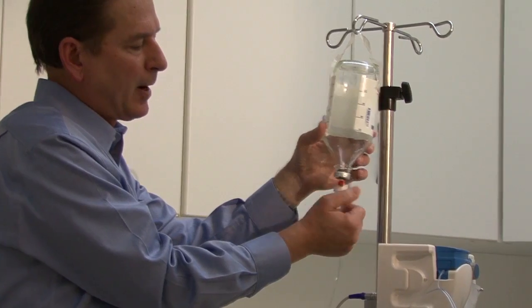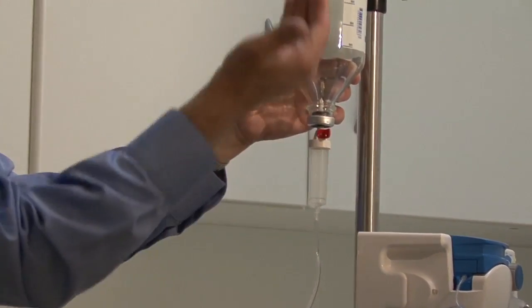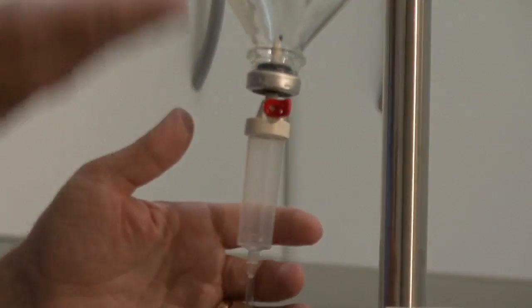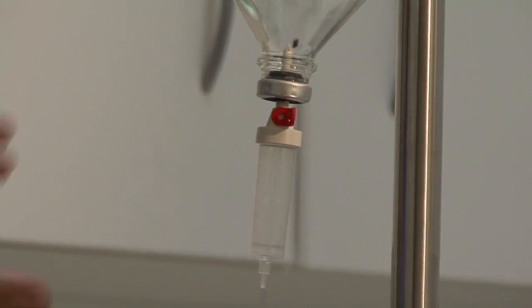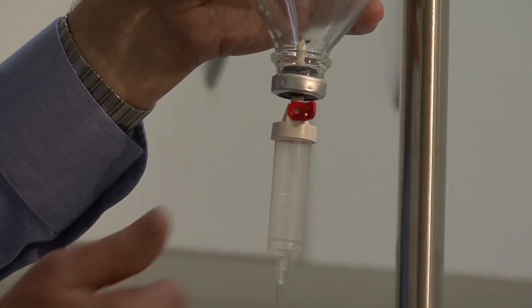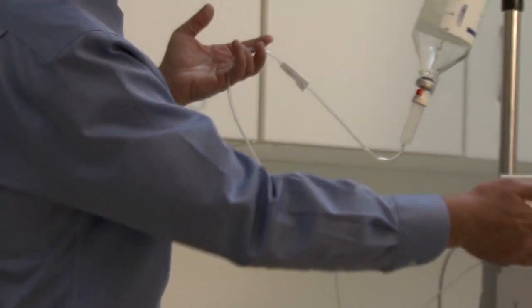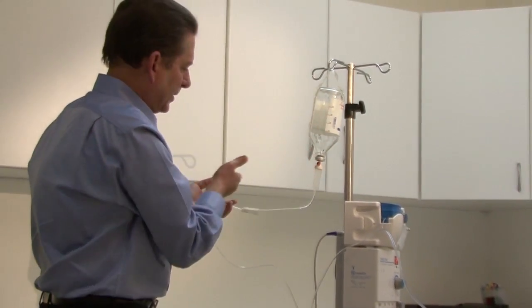We've got to make sure that we pop that open. If we don't open the air vent into the bottle, you'll notice that the fluid won't flow. So don't let that confuse you if it happens. Just remember to open the air vent and then you'll get the flow of the fluid. And then the final step is that we need to control the irrigation flow to the handpiece. It's coming from the bottle.